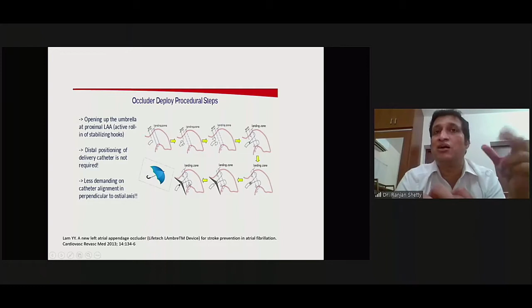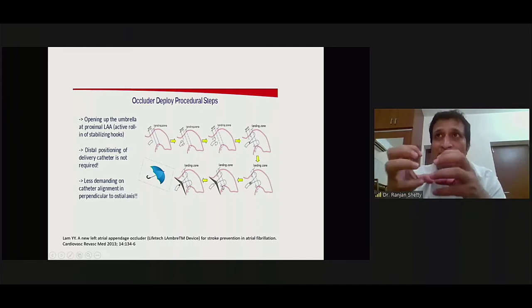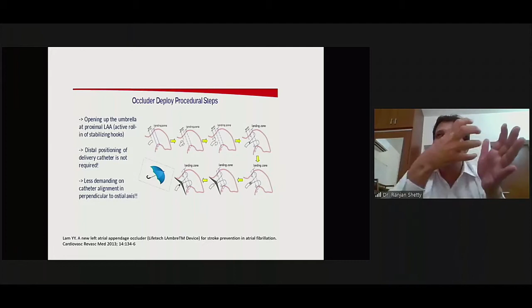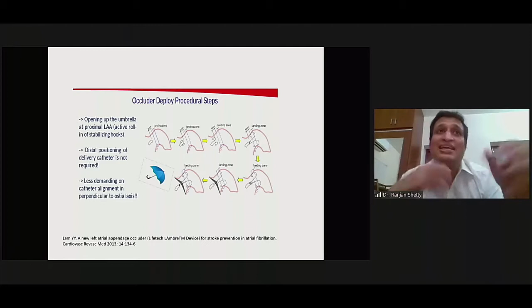Once you know the position, you push until you reach the landing zone. Once you are at the landing zone, start unsheathing the sheath with anti-clockwise rotation. As you do that, you realize that your device is now stuck, the lobule is stuck, and the disc is now covering. And most of the time, you need to have that little tug on the disc. It should look like a pacifier. The kid usually is not able to throw out the pacifier because there is a constant suction. So one of the mechanisms by which these devices are held in place is actually this mechanism.